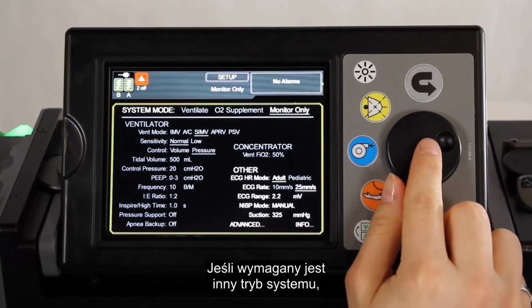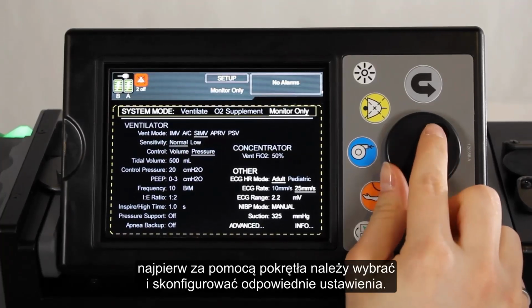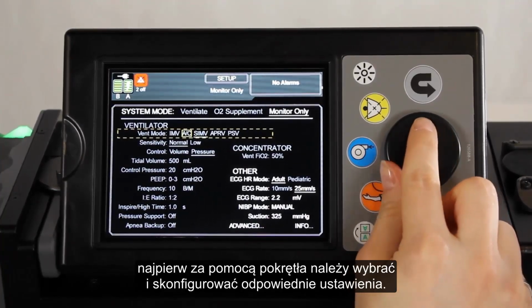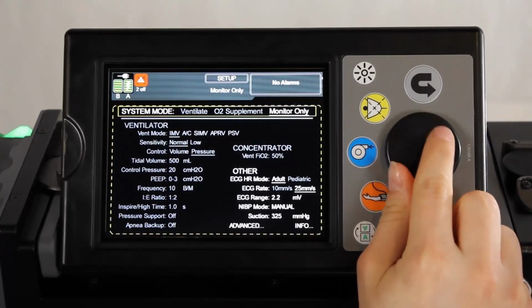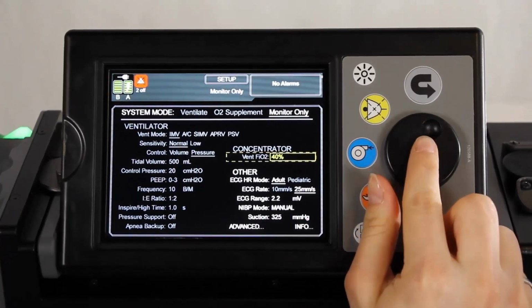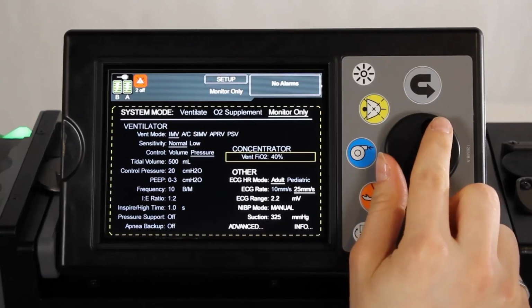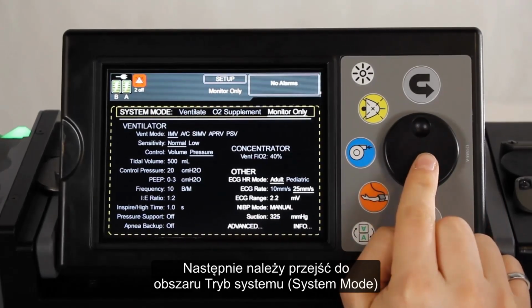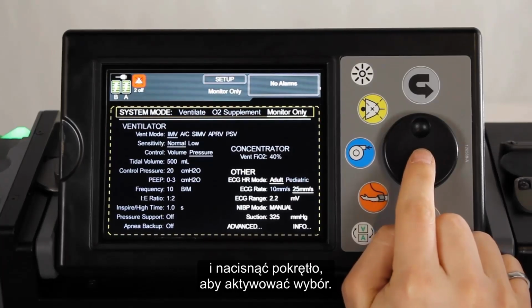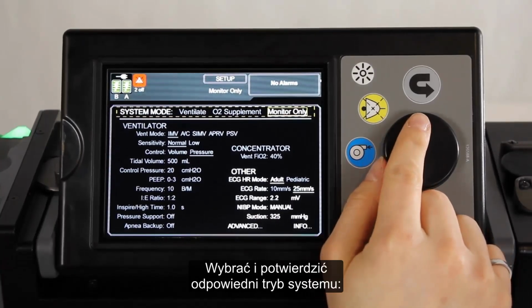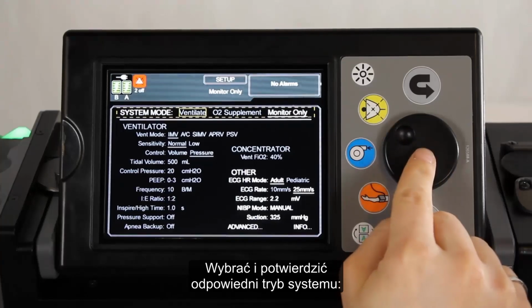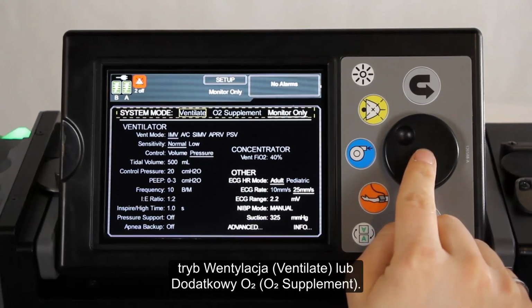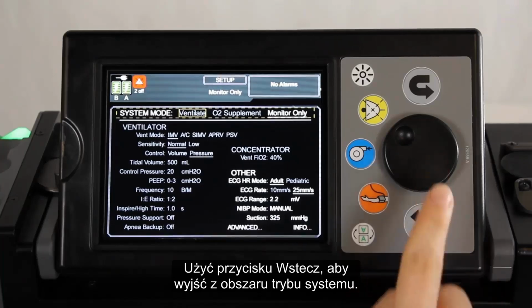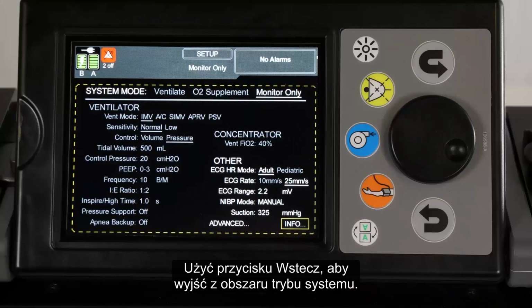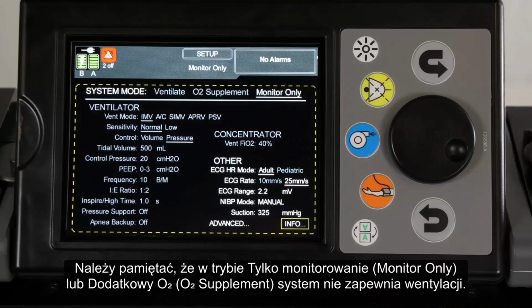If a different system mode is desired, first use the jog wheel to select and configure the appropriate settings. Then navigate to the System Mode area and press the jog wheel to activate the selection. Select and confirm the correct system mode, either Ventilate or O2 Supplement mode. Use the back button to exit the System Mode area. Note that the system does not ventilate in Monitor-only or O2 Supplement modes.